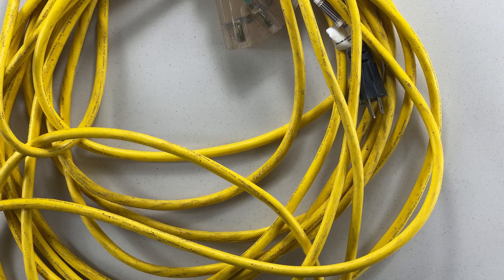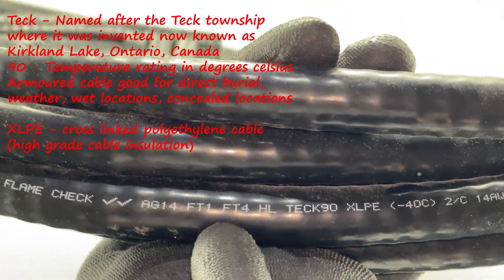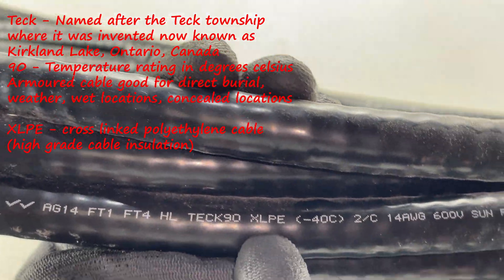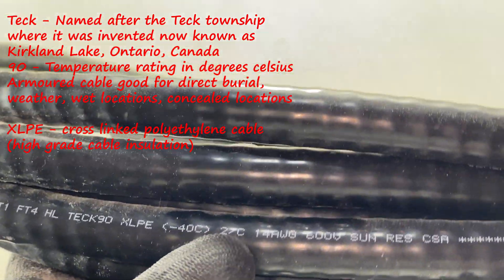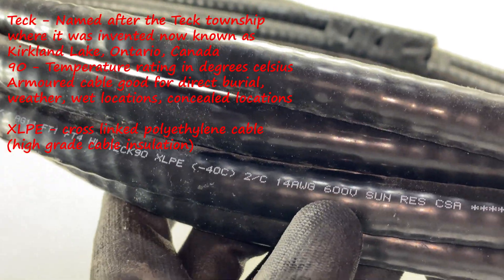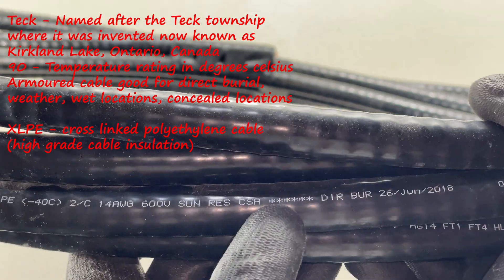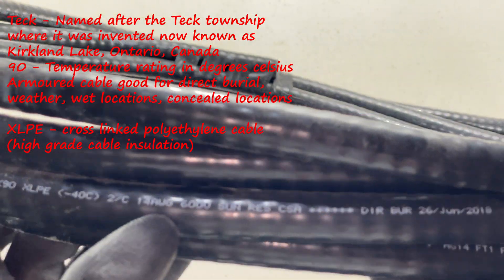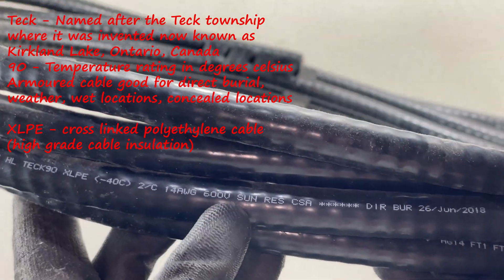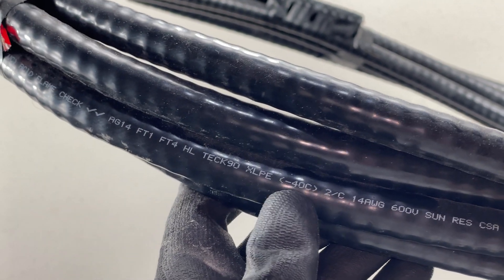Here we've got a TECK90 with FT1 fire rating up to FT4, XLPE insulation, good for negative 40 degrees, 2-conductor 14 AWG, good for 600 volts, with sun resistance. We even have the date it was manufactured, which is pretty cool. This is good for outdoor applications — the sun resistance and the negative 40-degree rating are really important.